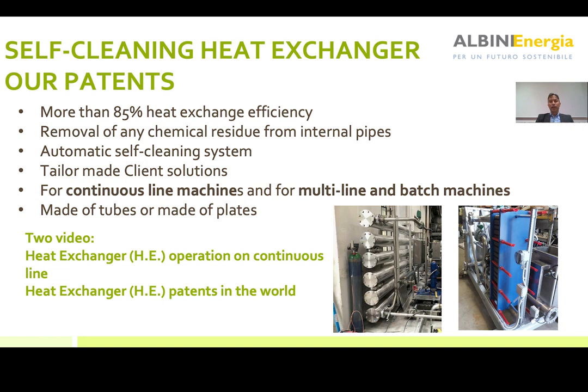The system was patented because, as you can imagine, the wastewater is full of suspended solids. So there is an automatic cleaning filter in front of this heat exchanger, and then there is a chemical cleaning system. That's the core of our patent.